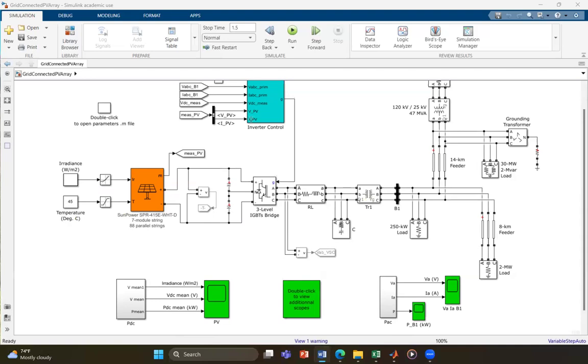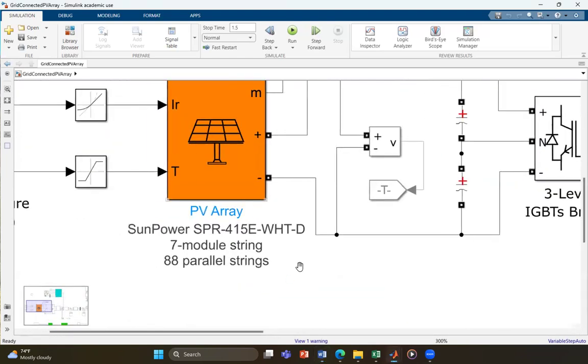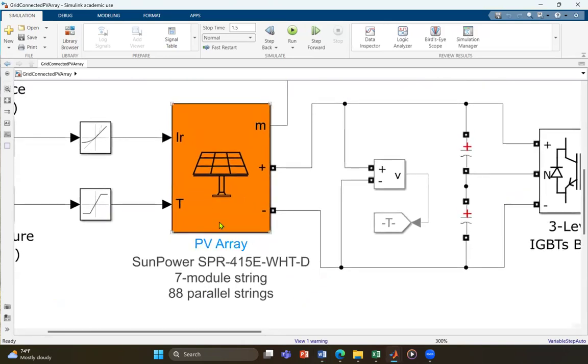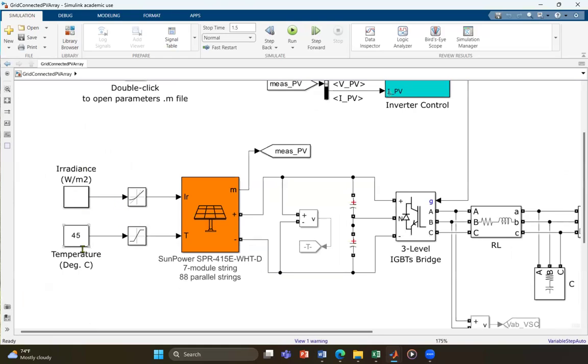Let's start with the key elements of the PV system. The first part is the PV array, which consists of multiple strings of PV modules — 88 parallel strings, each string with seven PV modules connected in series. The setup is designed to generate power from solar irradiance. Input parameters include irradiance in watts per square meter and temperature in degrees Celsius, which directly affect the output power of the PV array.